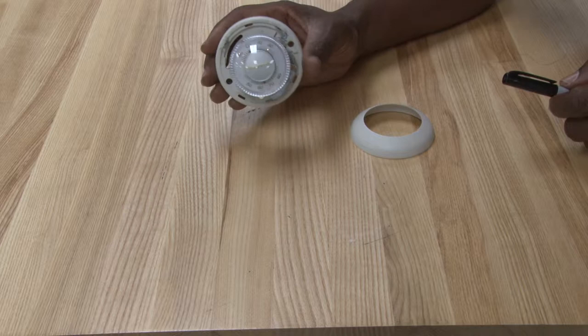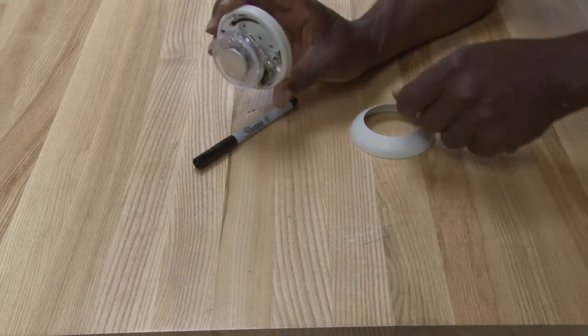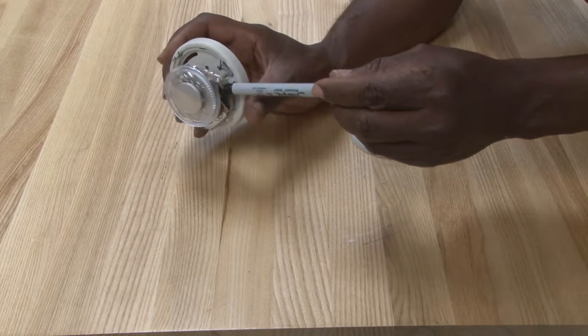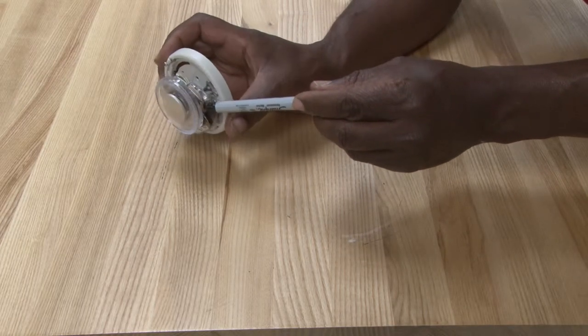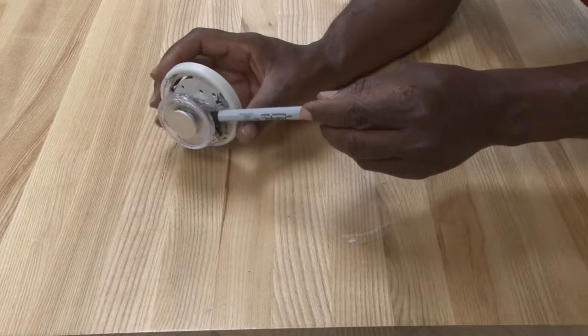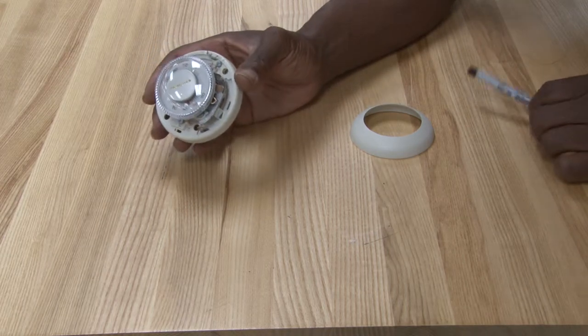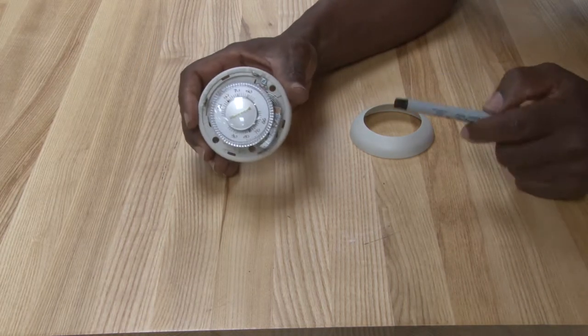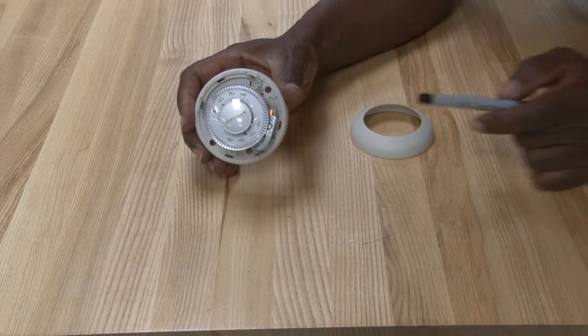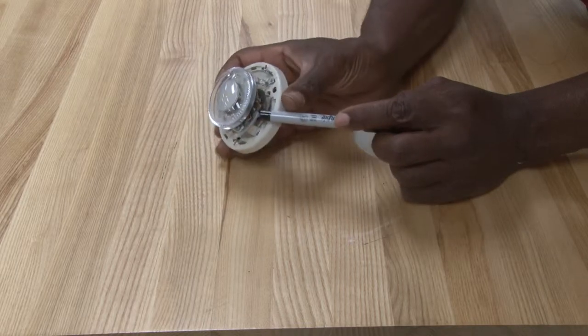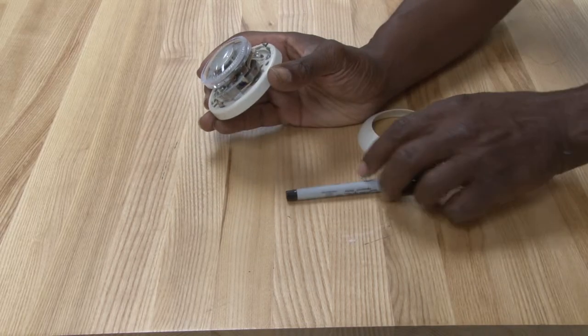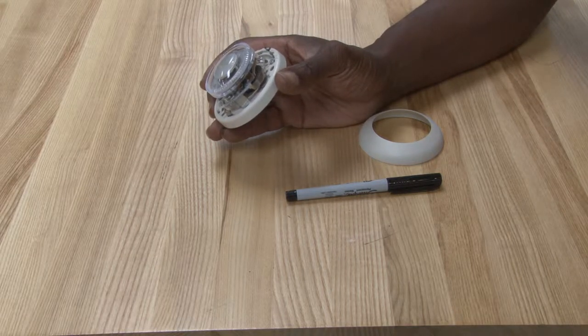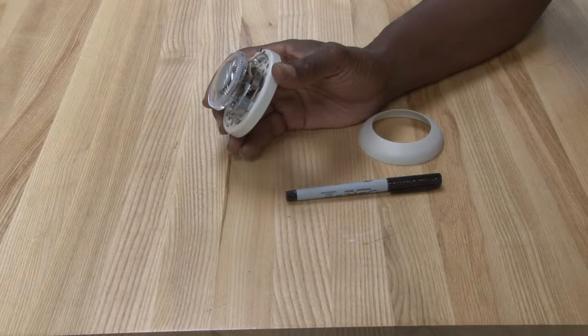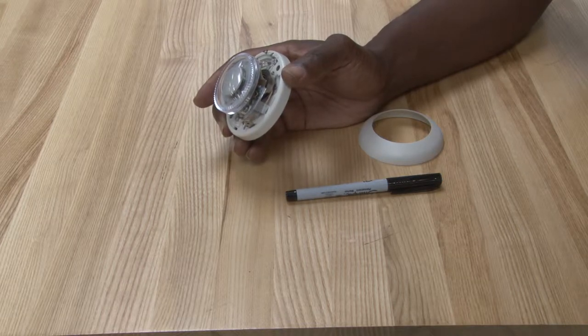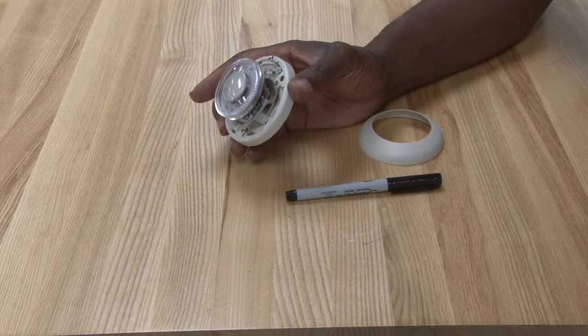And with this control, you see that if you turn it, you can maybe see the mercury moving around inside of this. If I move it back and forth, you could see it. Thermostats are designed to maintain the temperature, and the way it works, it senses the temperature in the room. This particular one has a bimetal coil, and this bimetal coil consists of two different metals, and when there's a temperature change, it will warp the bimetal and cause movement. It's in a coil, so it would expand or contract based on the movement.